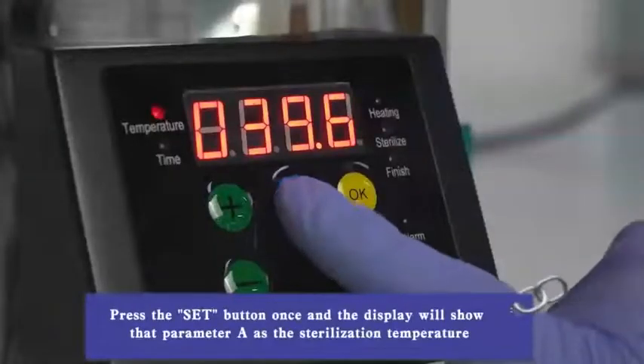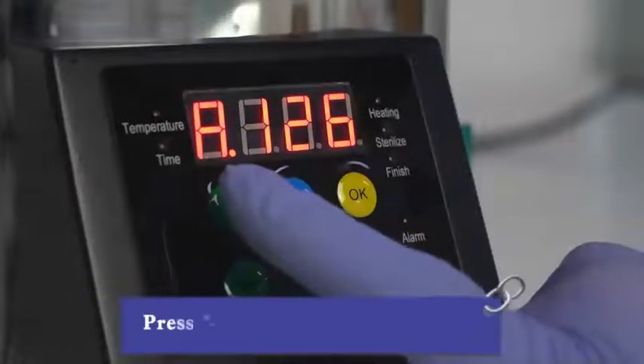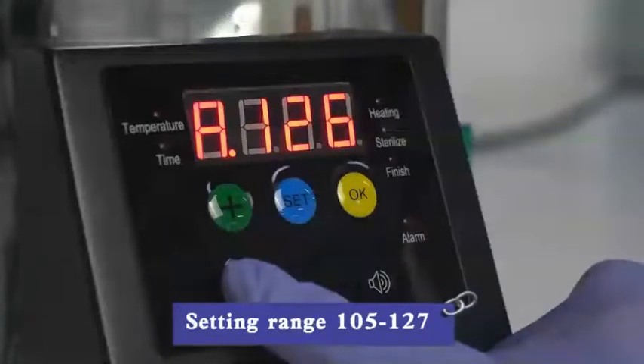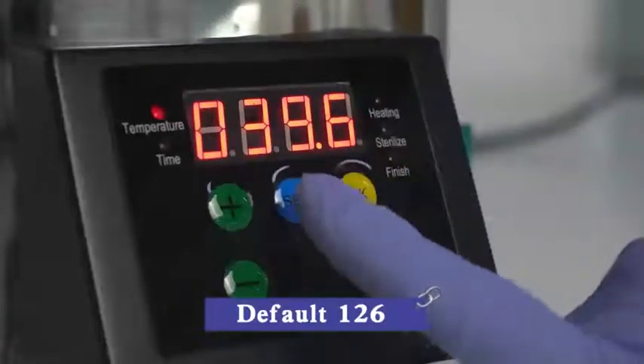Press the SET button once and the display will show parameter A: sterilization temperature. Press plus or minus to modify the value. Press OK to save and exit. Set in range 105 to 127; default is 126.